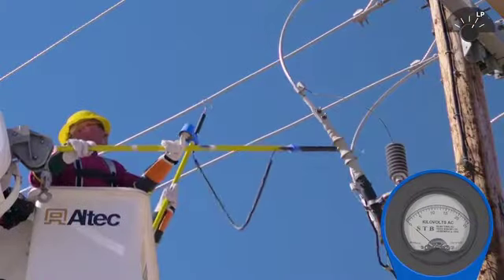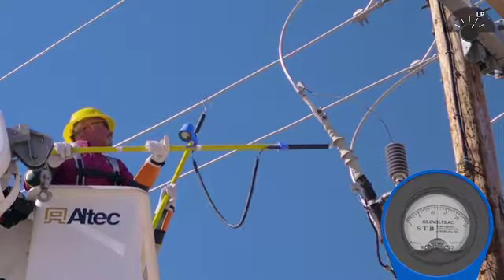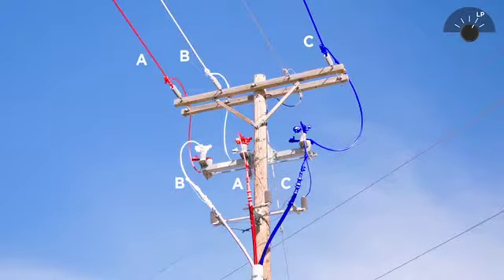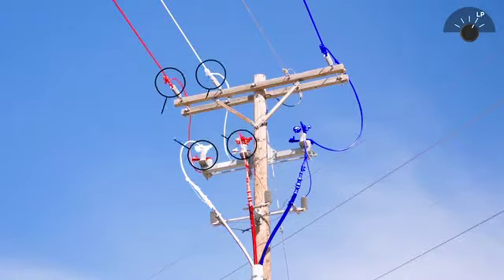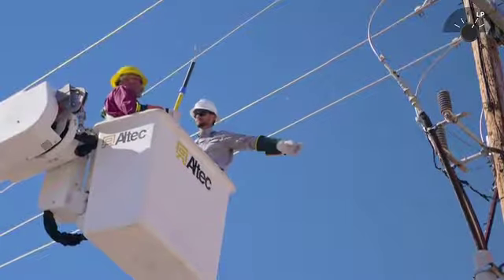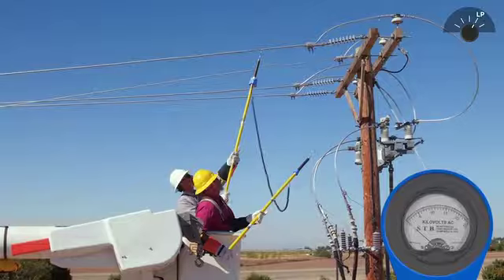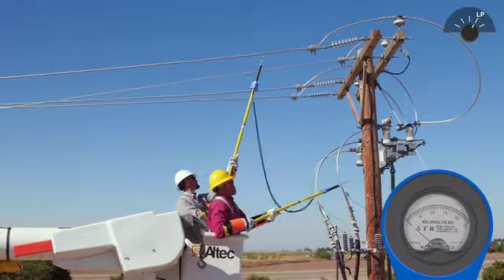If the meter shows voltage between corresponding conductors of an open point, the phase sequence has been changed. If these conductors were connected, a circuit fault would occur. This means the troubleshooting process must begin. Once the proper phasing sequence over the open point is proven, the line can be closed.